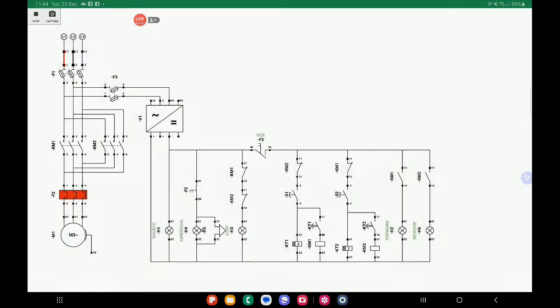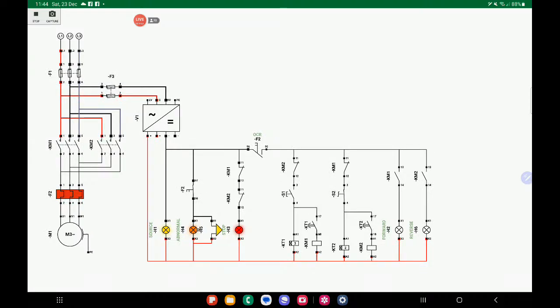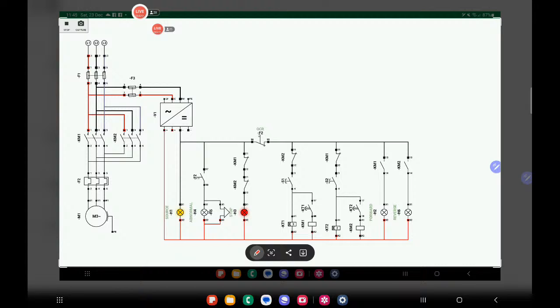Let's say in a certain condition wherein you do not have a forward operation, because this circuit is an electrical circuit diagram wherein it operates in, okay, let's reset F2. Let's try to run S2. Now it's in reverse direction, right? The electrical motor is running in reverse direction. I'll stop it. I'll start S1, and now it's running in forward direction. And I'll stop it. Let's say your forward operation, the electrical motor did not run. So you're having a problem with your forward operation. So what would be the first step that you need to do?